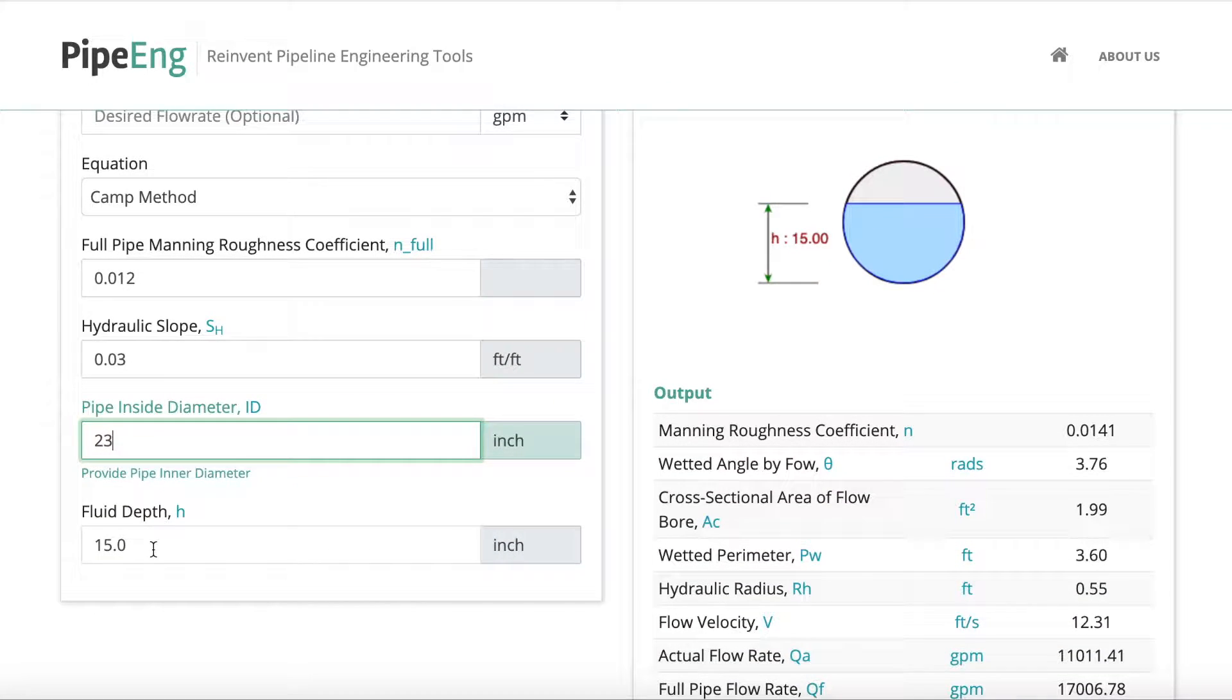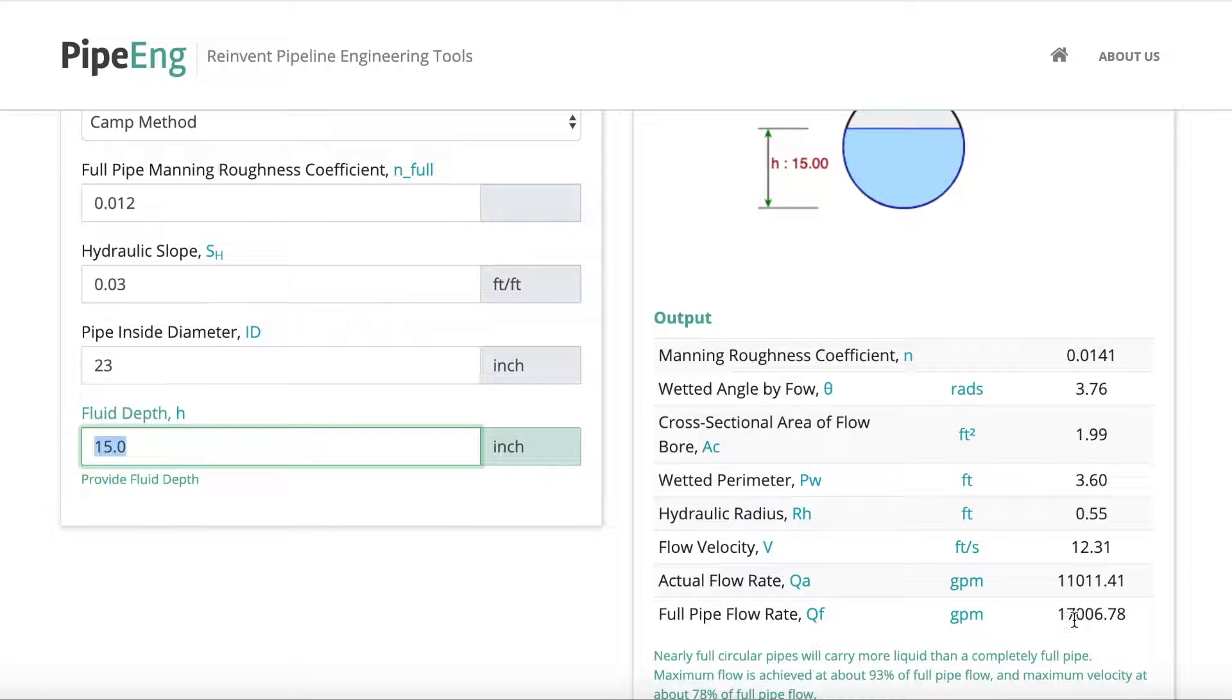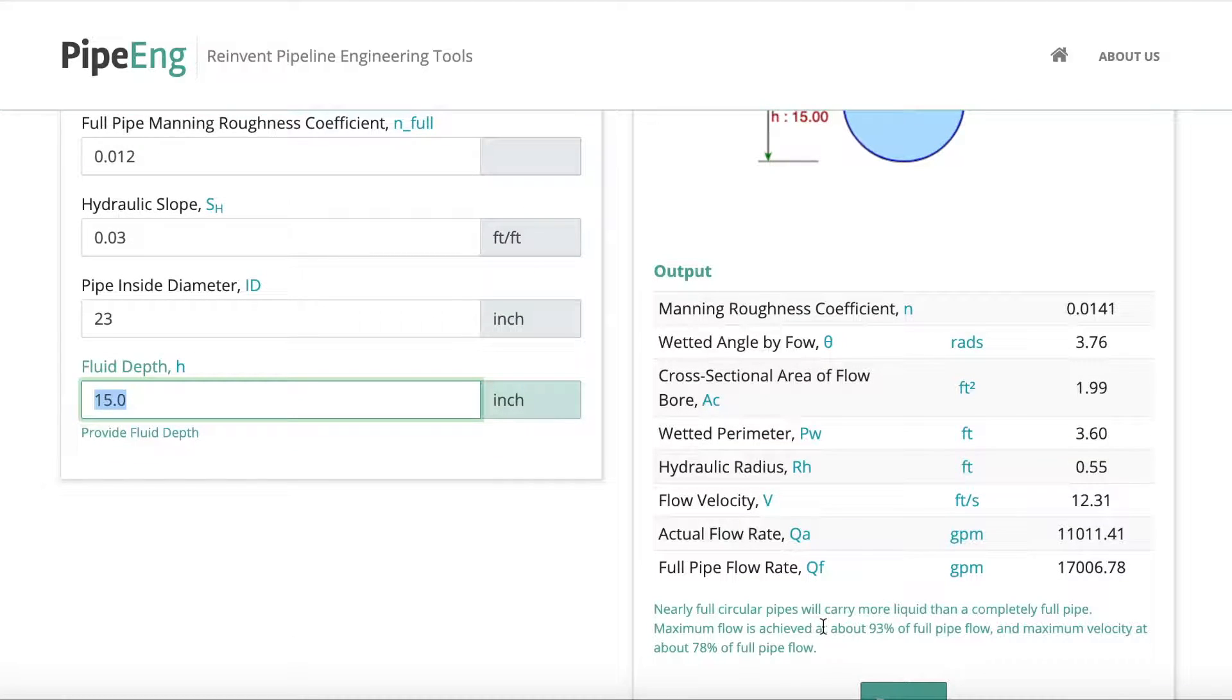And the fluid depth is, you can either know the fluid depth and want to know the actual flow rate, or you want to check the actual capacity. So the full pipe flow rate here is about 17,000 gallons per minute. You can use this as the capacity, but please note that actually the maximum flow is achieved at about 93% of full pipe flow, not actually full pipe flow. So that's why a lot of times if you play with the fluid depth, you will find actually when it's full, the pipe is actually less than the maximum. You get actual flow when it's not full that is actually more than the full pipe flow rate.